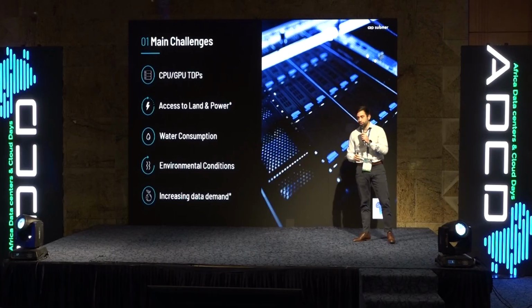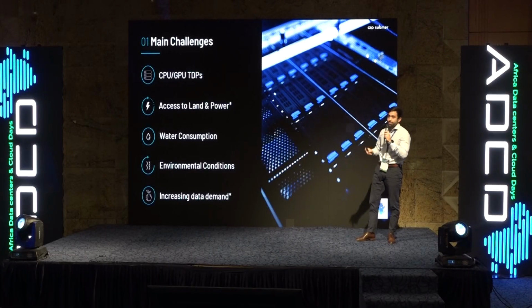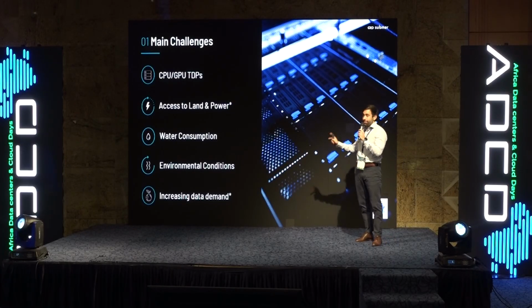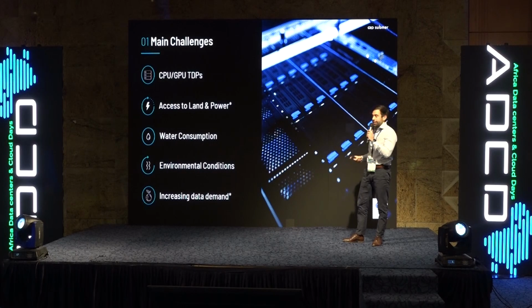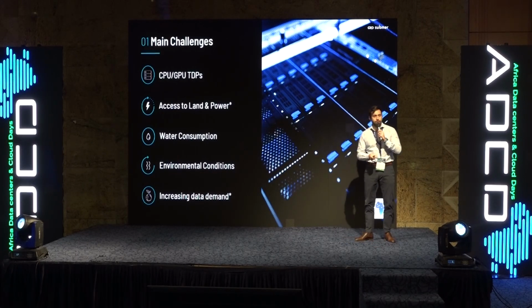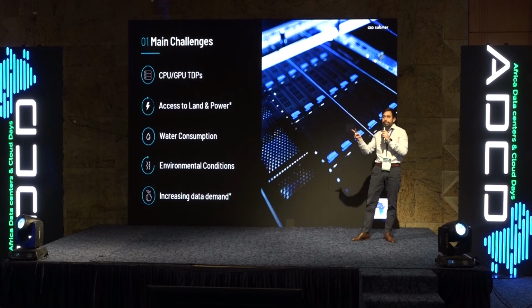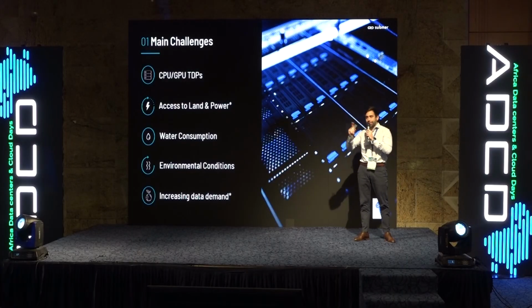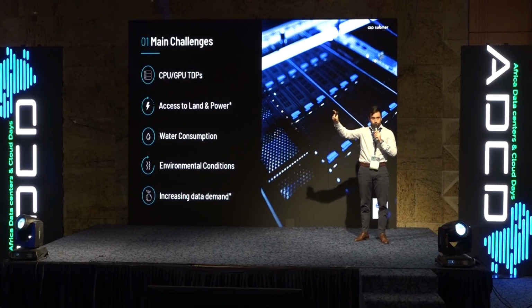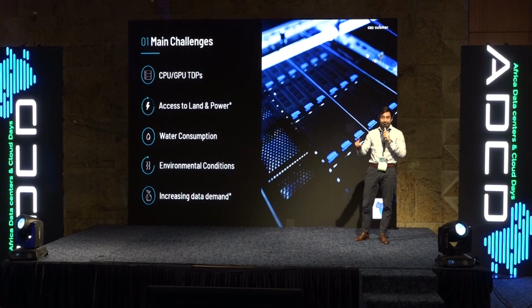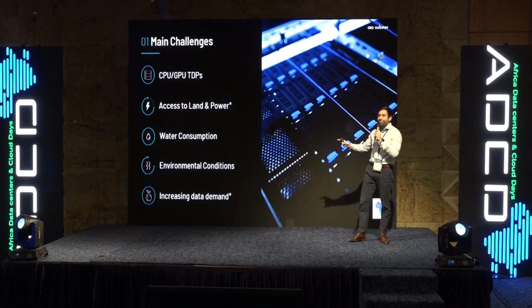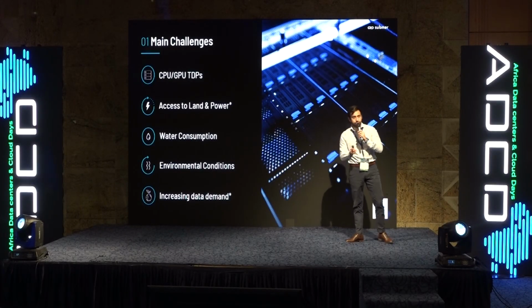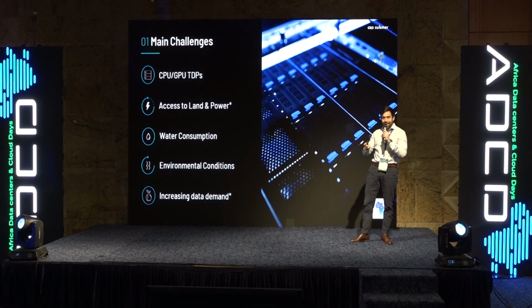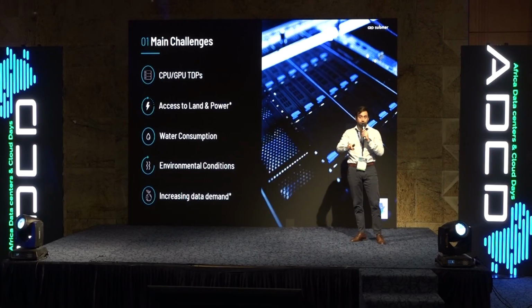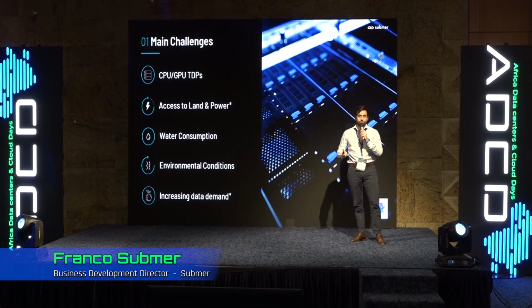Number 4 is the environmental conditions, and this applies mainly to Northern Africa. Tomorrow I'm going to Egypt, where, you may know the term PUE, power usage effectiveness, the ratio between the total consumption in your data center and the IT consumption. They have a PUE of 2, meaning that per each 1,000 watts of ICT, they need 1,000 watts more for the electrical and mechanical infrastructure.